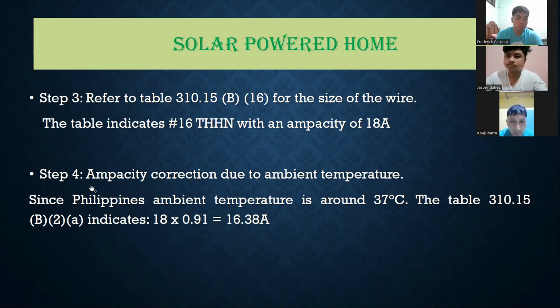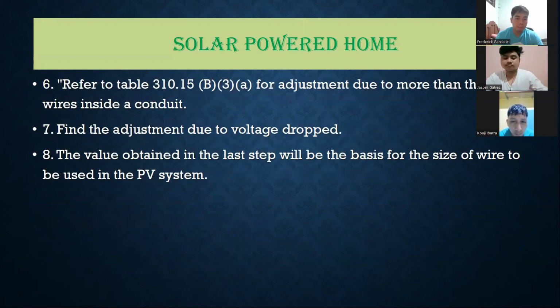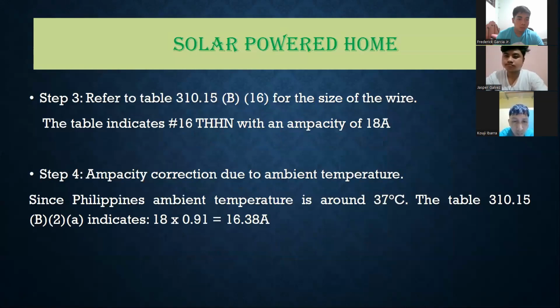Now, step 4, we correct for ambient temperature. Since the Philippines ambient temperature is 37 degrees Celsius, we use the table again. Here's the table. This part of the table right here, 37 degrees, around here, we multiply for THHN, the multiplication factor of 0.91 here. Now we multiply that 18 ampacity of the number 16 THHN wire with 0.91, and we get 16.38 amps.